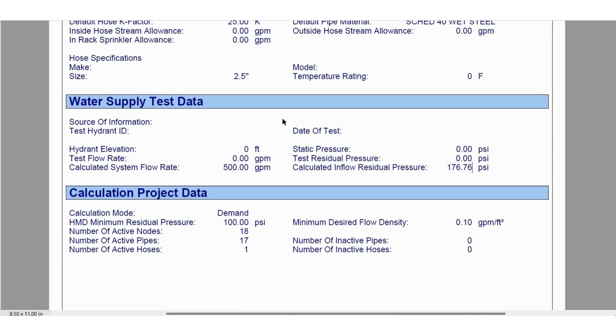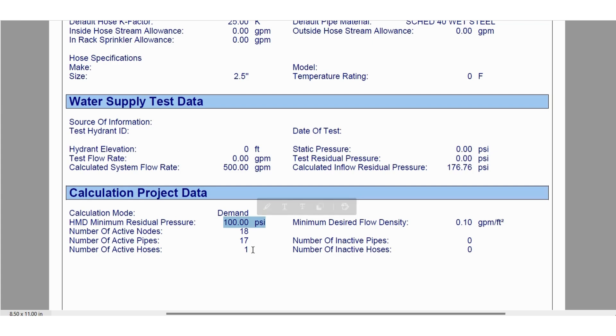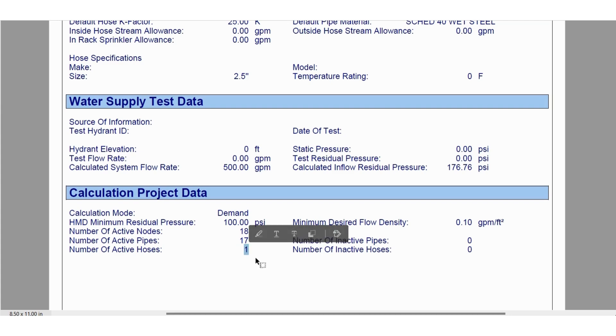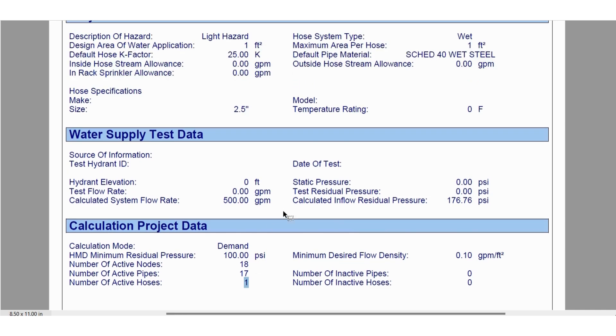Looking at the cover sheet, we have mentioned that the minimum residual pressure required at the hydraulically most demanding landing valve shall be 100 PSI. However, the calculation report shows the number of active hoses as one only, even though we have considered two landing valves. I will explain this in a few minutes.